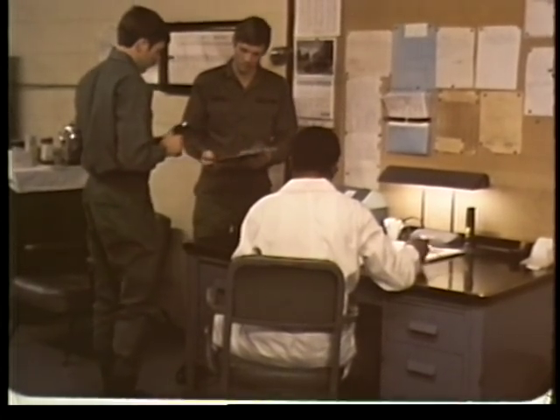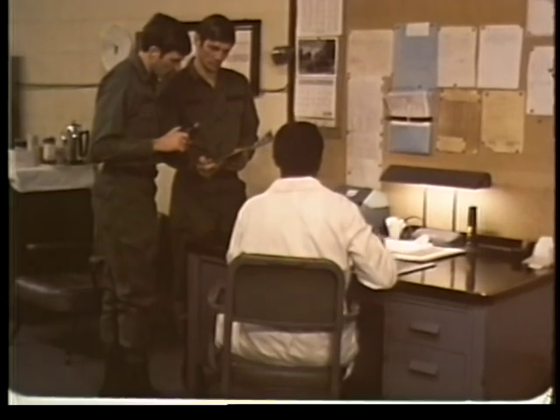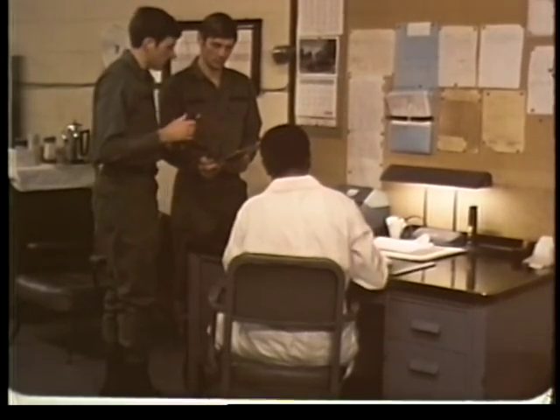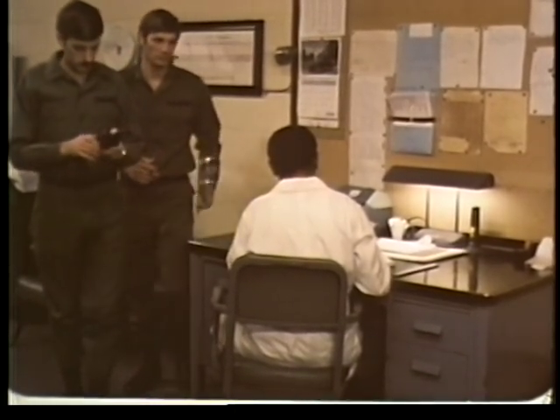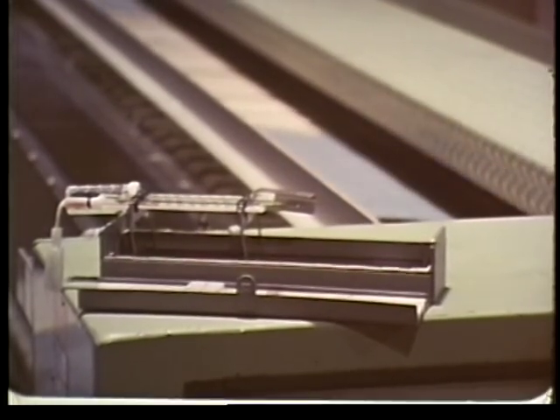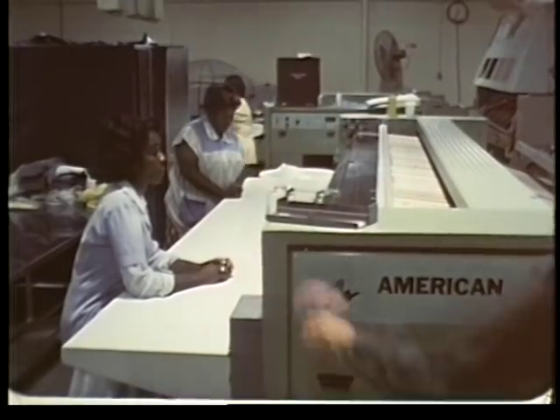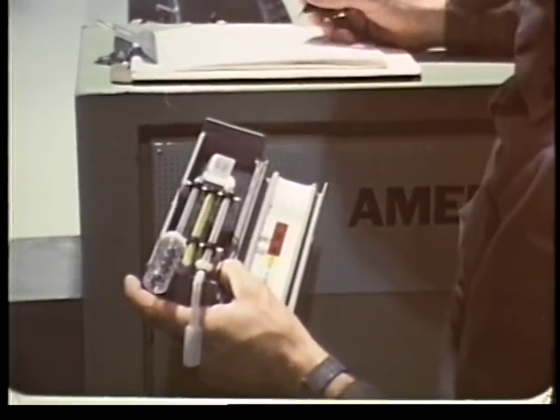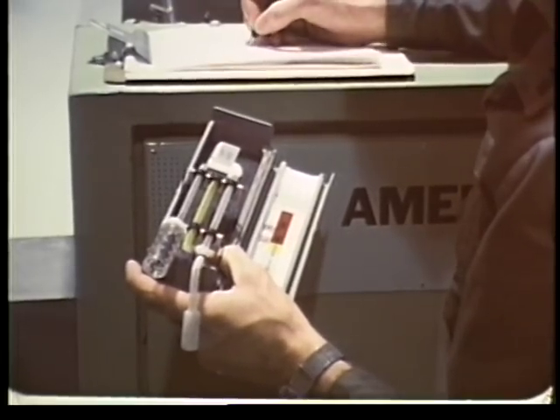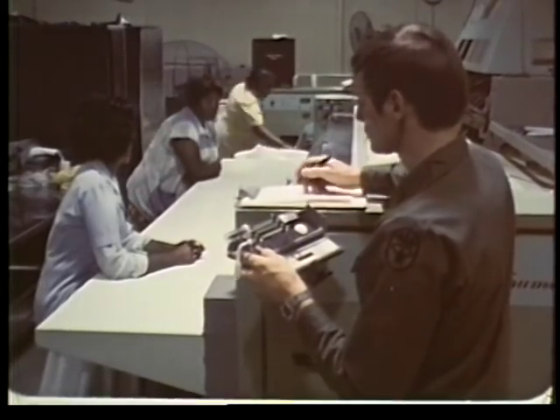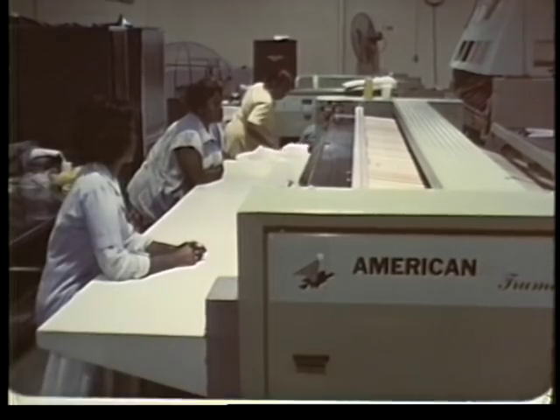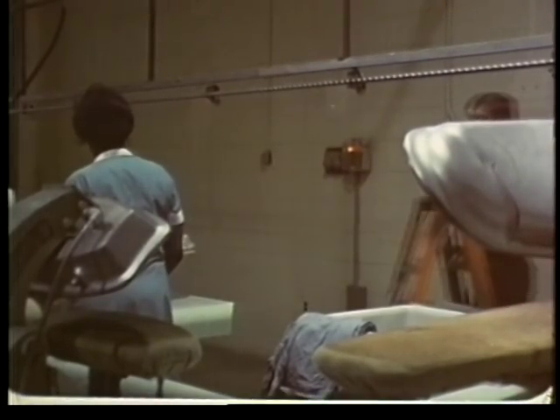By now, it's probably about time to take your first series of temperature readings. Since in this case, temperatures are being taken indoors, you're only interested in reading two of the three thermometers, the wet bulb and the black globe. Later, you'll combine these readings to determine the WBGT index value.